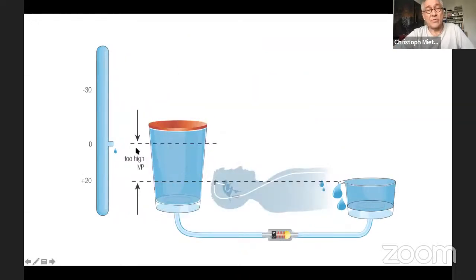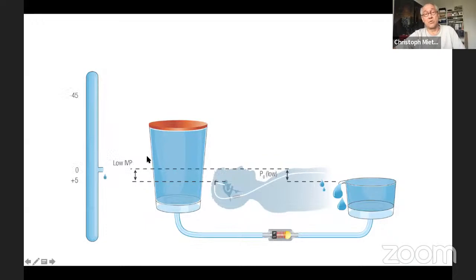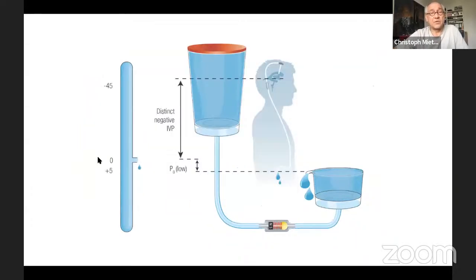But now in the lying position, the pressure is by far too high, not physiological, and possibly leads to a problem. If you lower the IVP for the lying position, this is fine, you get rid of the problem, but in the upright position, as this is very low, you get a more distinct negative IVP, and hereby a very high risk of creating problems with overdrainage.